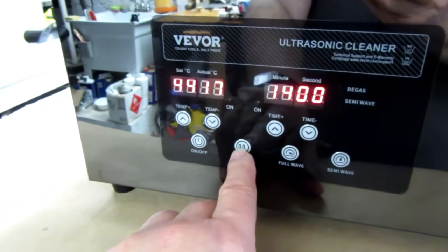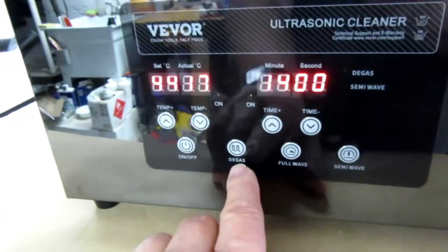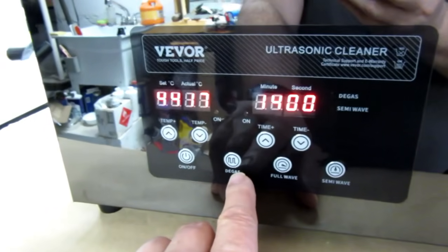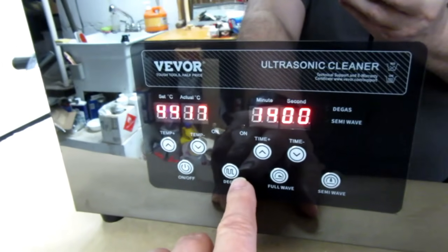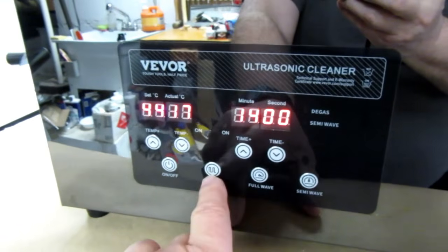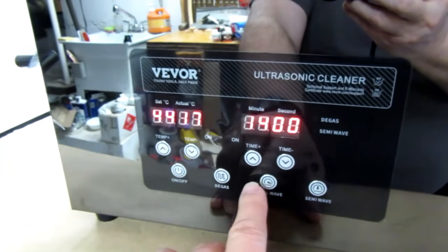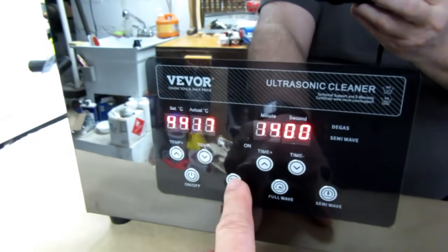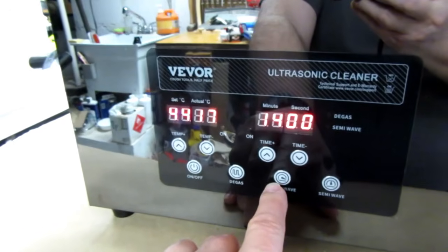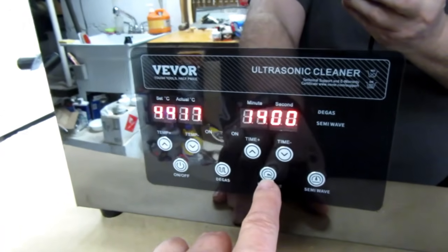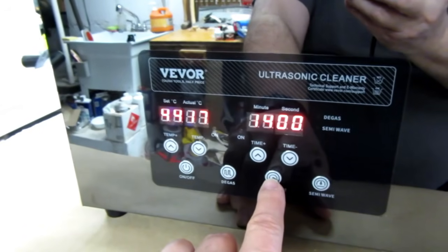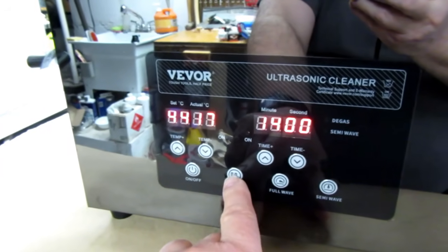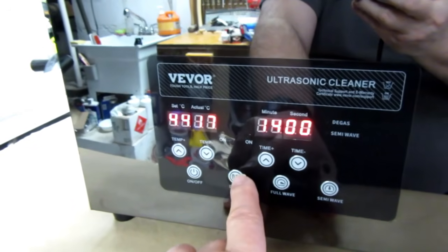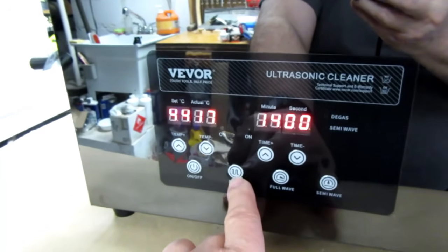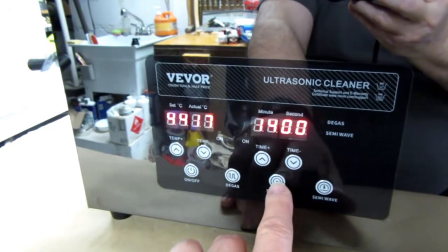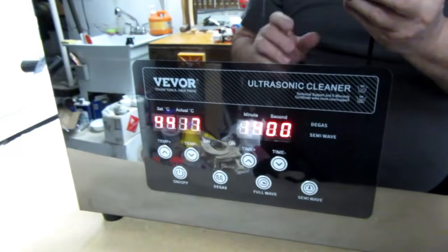Well, there's also this feature called degas, or I've heard people say degas, like it's a Spanish name or something. It's short for degasification, degassing, different ways of saying it. What it's doing is it's running it in full wave mode, and it's cycling through two different ways of doing the full wave mode. On these basic Vevor models, Vevor says they don't put it in their manual, but they told me that it's going 6 seconds on and 3 seconds off, 6 seconds on, 3 seconds off. So it's alternating between just being off and being in full wave mode.